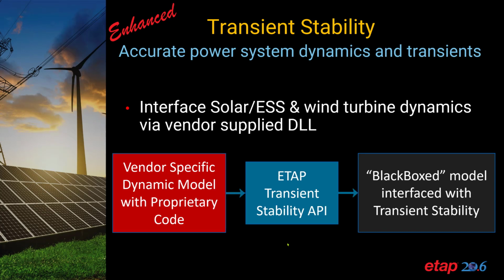ETAP transient stability also includes accurate power system dynamics and transients based on vendor-specific dynamic models that have proprietary code. The ETAP transient stability API has been expanded to take the vendor-specific dynamic models that have this proprietary code and black box them such that they can be interfaced with transient stability itself, allowing us to use vendor-supplied DLLs within transient stability simulation and allowing for better grid code and system assessment in terms of dynamics and stability.